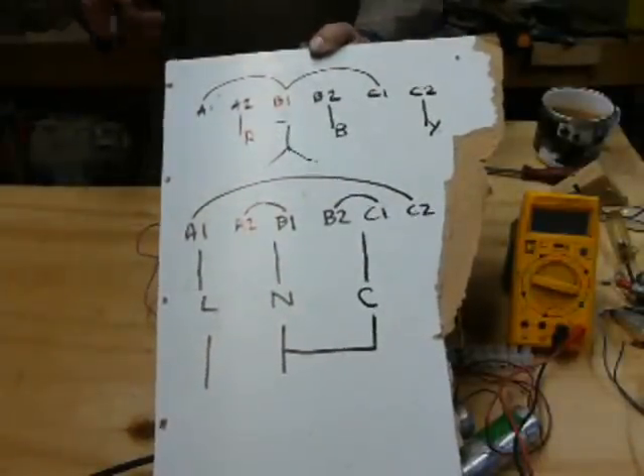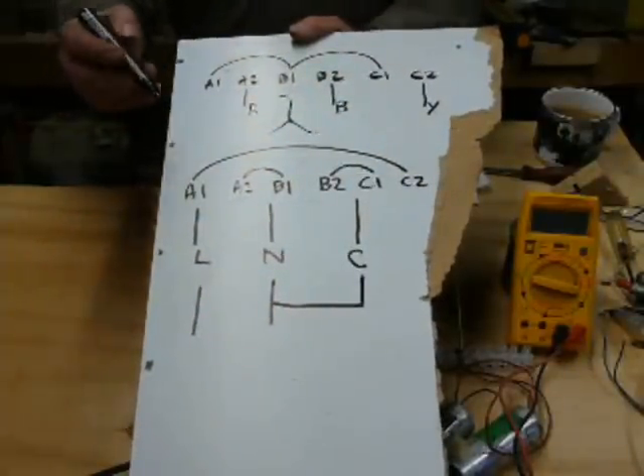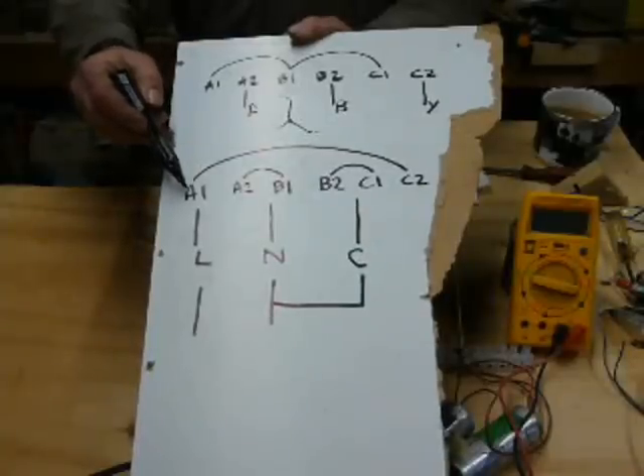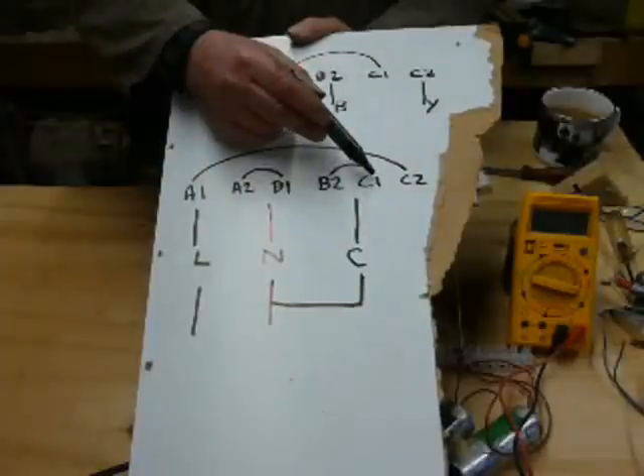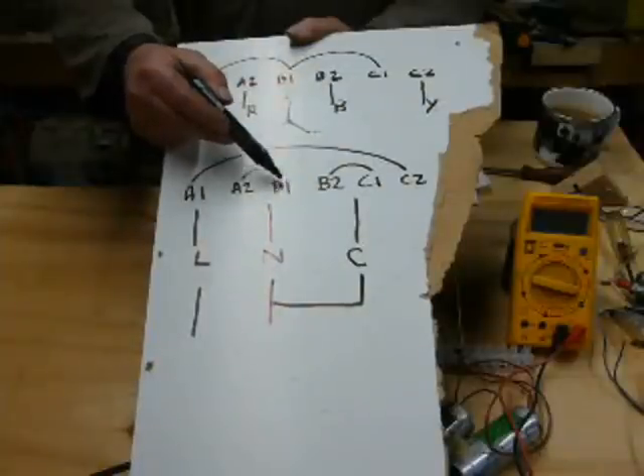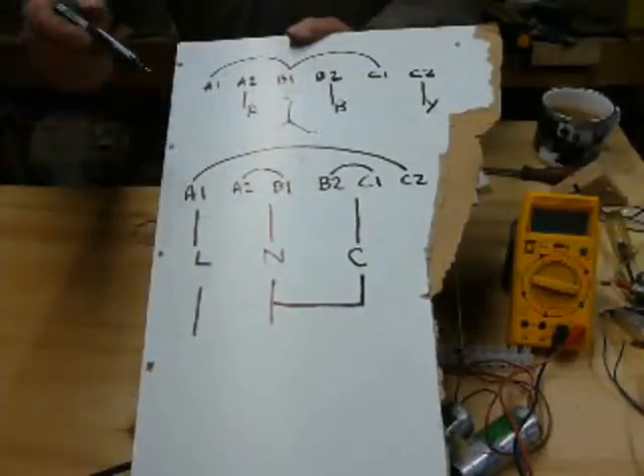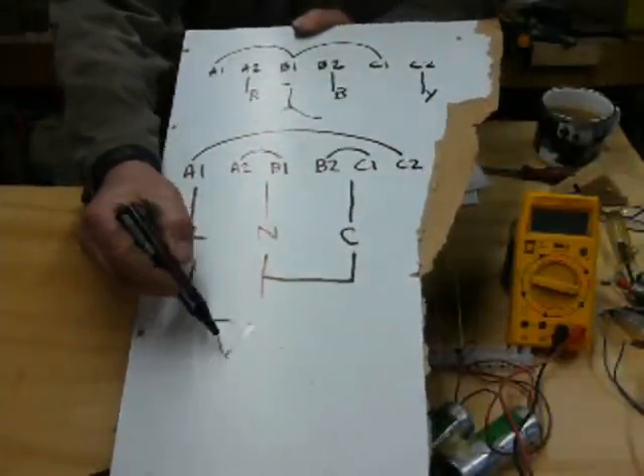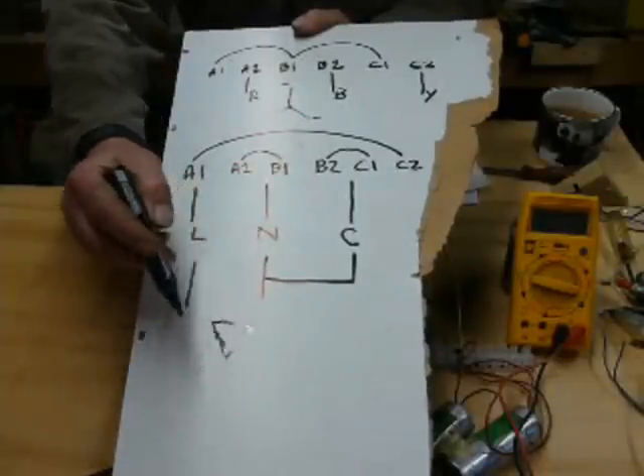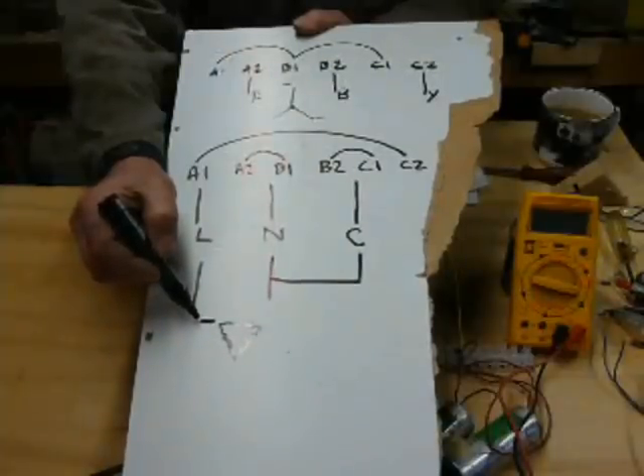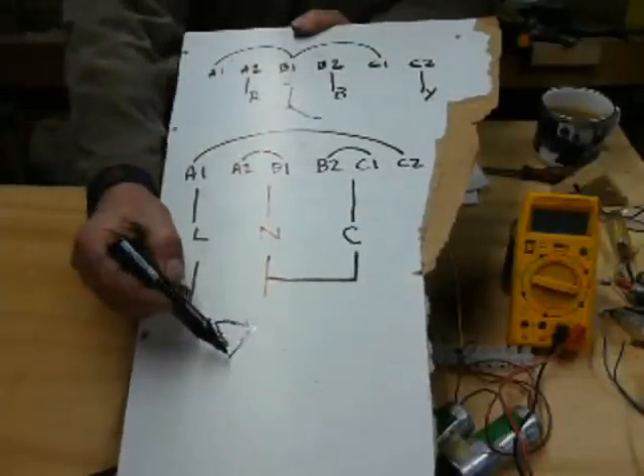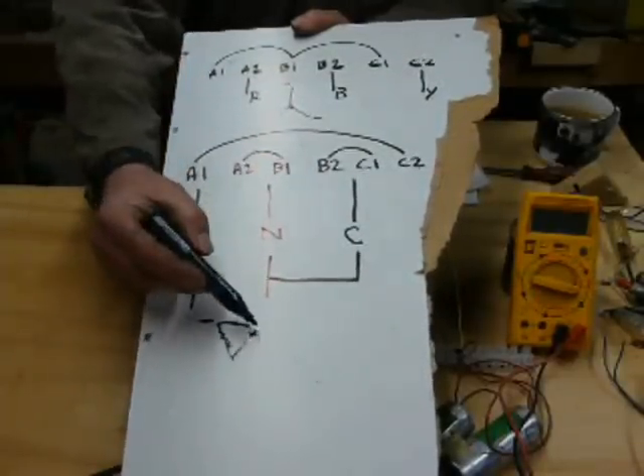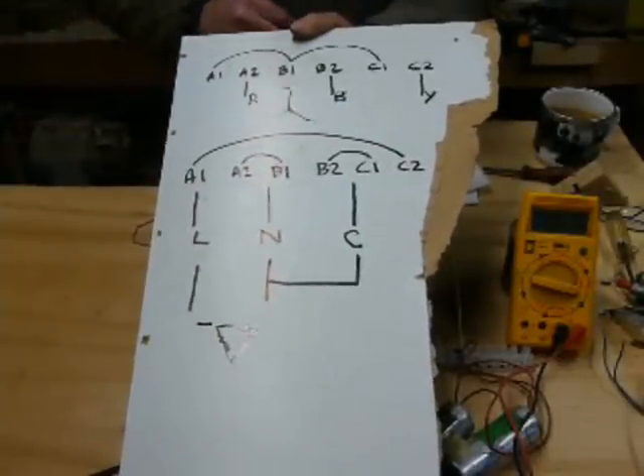So I had to think about this for a short while. And I thought, alright, okay, that makes sense. So I took those links out and put these links in. A1 to C2 through the coil to C1, then a link to B2 through the coil to B1, then B1 a link to A2 through the coil to A1. So what we've got now is delta. There's the coils. And this is A1 and C2 because there it's linked through. That one is A2 and B1 because there's a link, and that one is B2 to C1. So hopefully that makes sense.